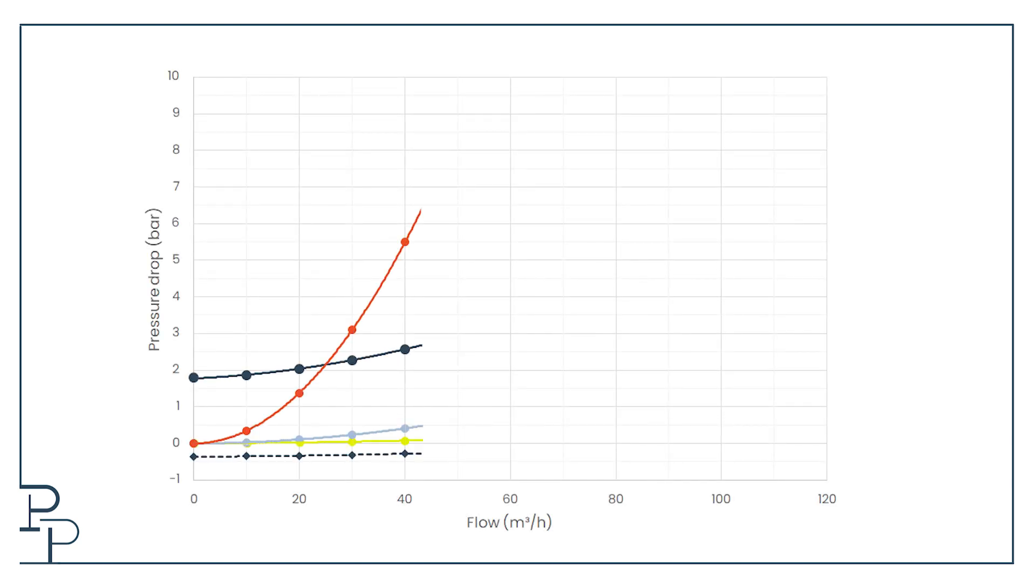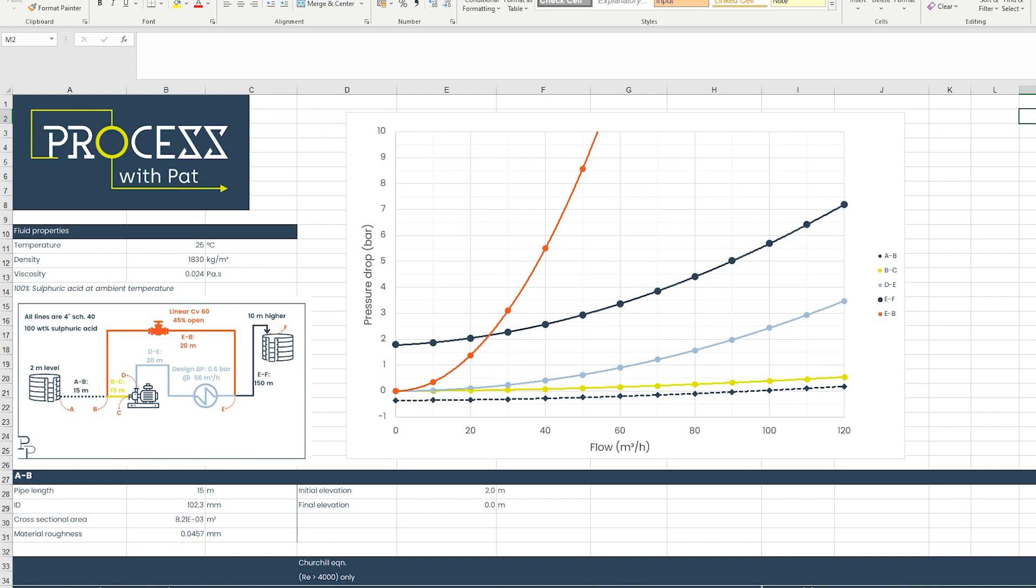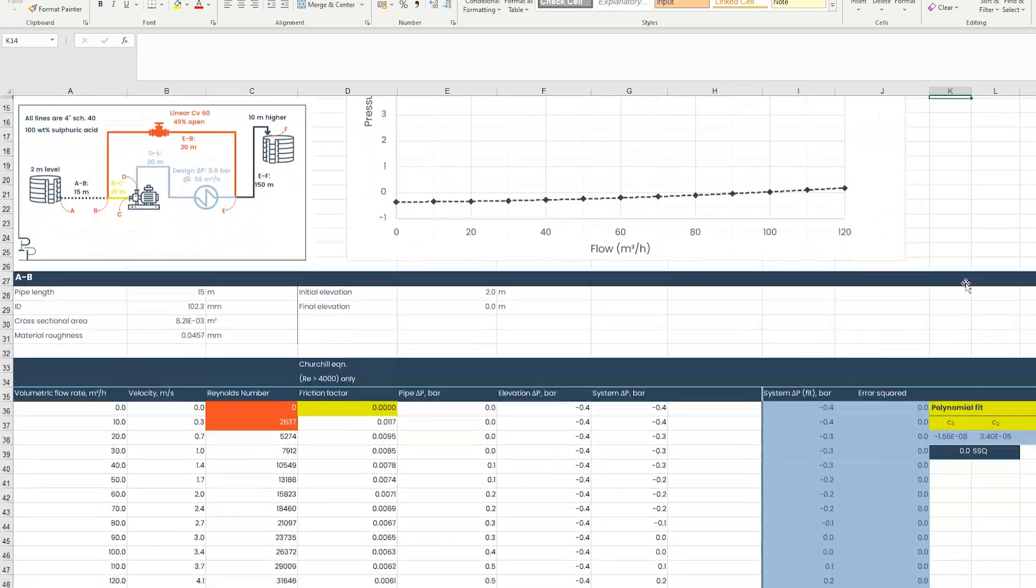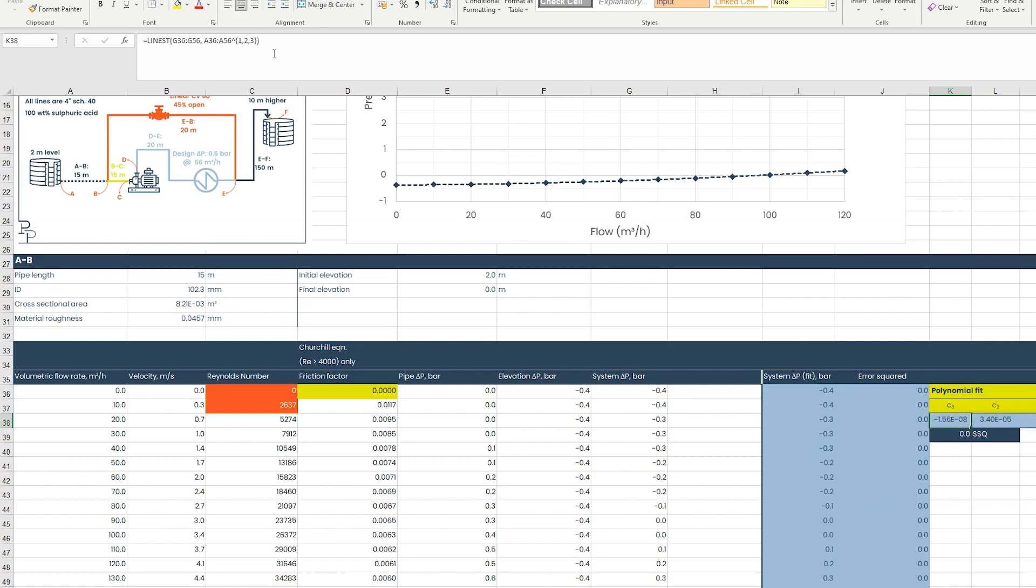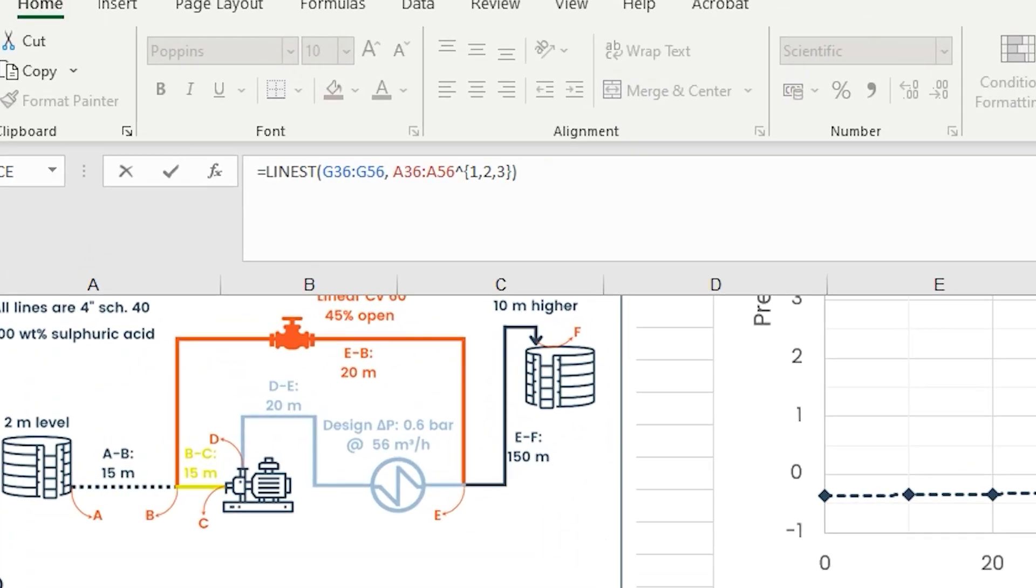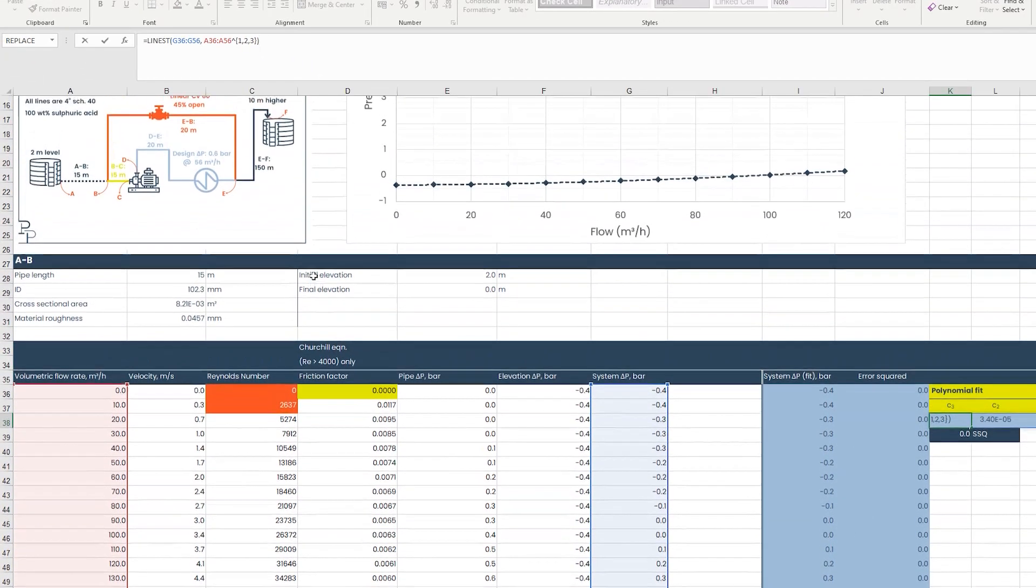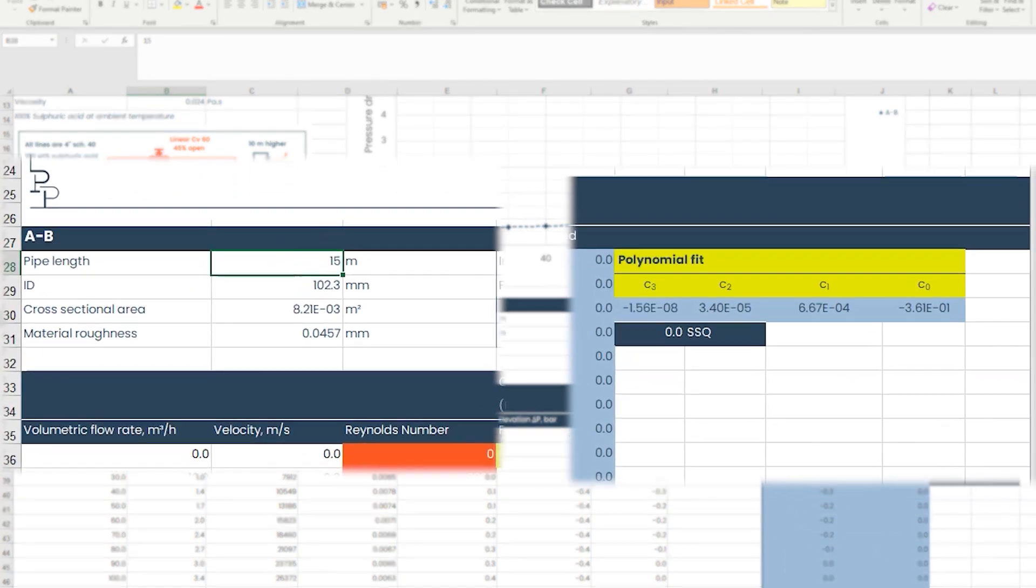Now I have my geometry and my fluid defined, I'm ready to start building system curves. Here I've got individual system curves for each of the sections we've just described. I'm hoping that if you've come this far, you don't need this explained to you. But if you do need help, you can get access to the file in the link in the description. One thing I like to do is use the LINEST function to automatically get the coefficients of any polynomial that's fitted to the system curve. That way if I change anything, the coefficients automatically get updated and I use those to calculate pressure drop elsewhere.